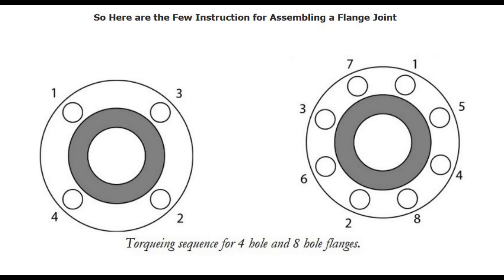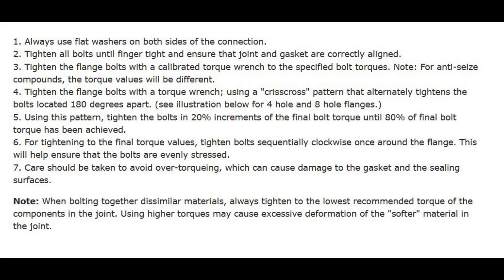Here are the instructions for assembling a flange joint. Number 1: Always use flat washers on both sides of the connection. Number 2: Tighten all bolts until finger tight and ensure that the joint and gasket are correctly aligned. Number 3: Tighten the flange bolts with a calibrated torque wrench to the specified bolt torques. Note: for anti-seize compounds, the torque values will be different.